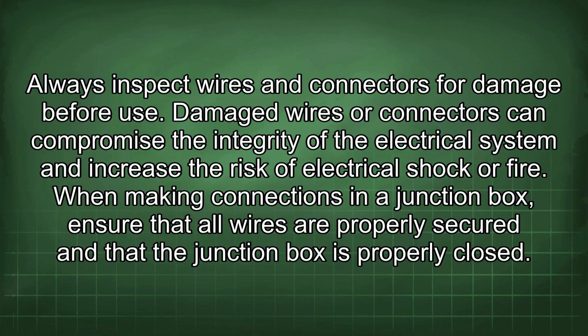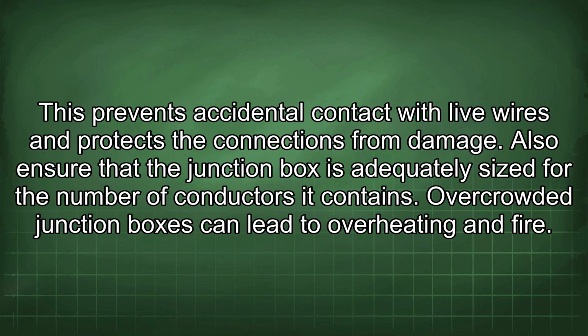Damaged wires or connectors can compromise the integrity of the electrical system and increase the risk of electrical shock or fire. When making connections in a junction box, ensure that all wires are properly secured and that the junction box is properly closed. This prevents accidental contact with live wires and protects the connections from damage. Also ensure that the junction box is adequately sized for the number of conductors it contains. Overcrowded junction boxes can lead to overheating and fire.